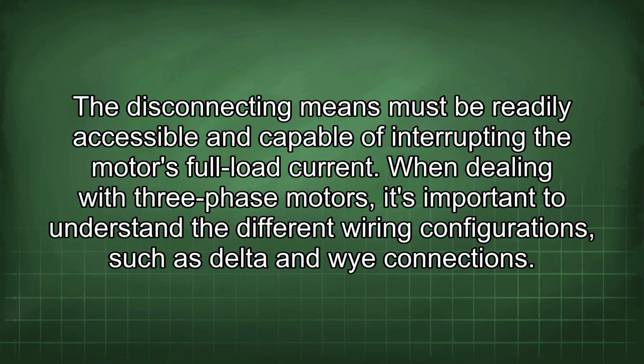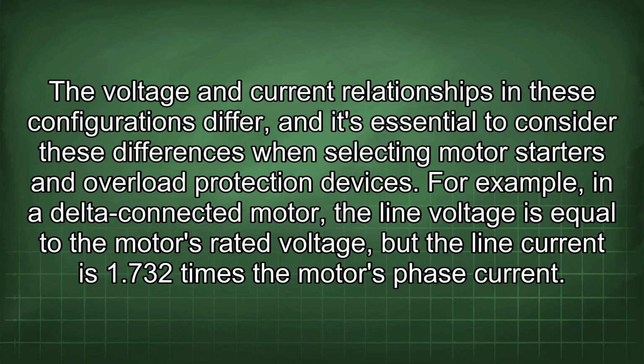When dealing with three-phase motors, it's important to understand the different wiring configurations, such as delta and Y connections. The voltage and current relationships in these configurations differ, and it's essential to consider these differences when selecting motor starters and overload protection devices. For example, in a delta-connected motor, the line voltage is equal to the motor's rated voltage, but the line current is 1.732 times the motor's phase current.